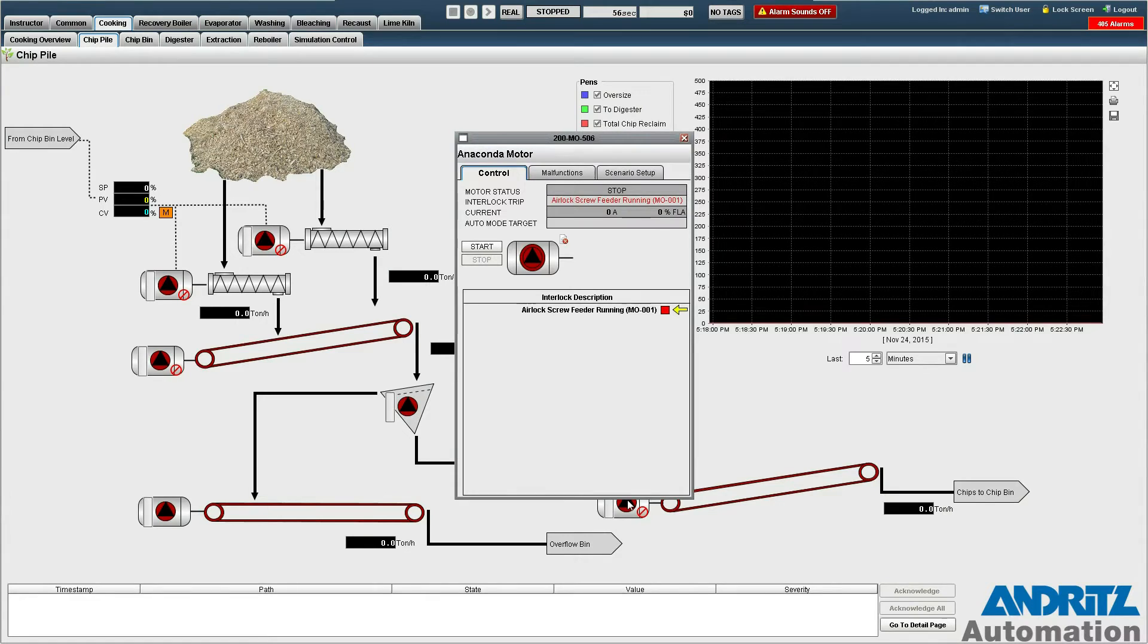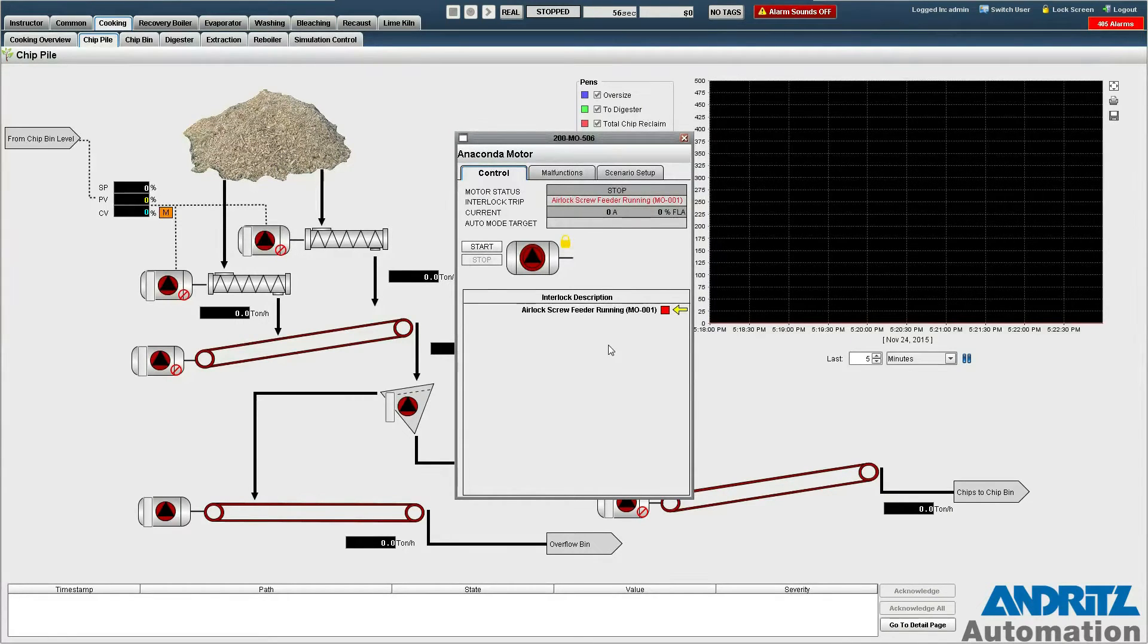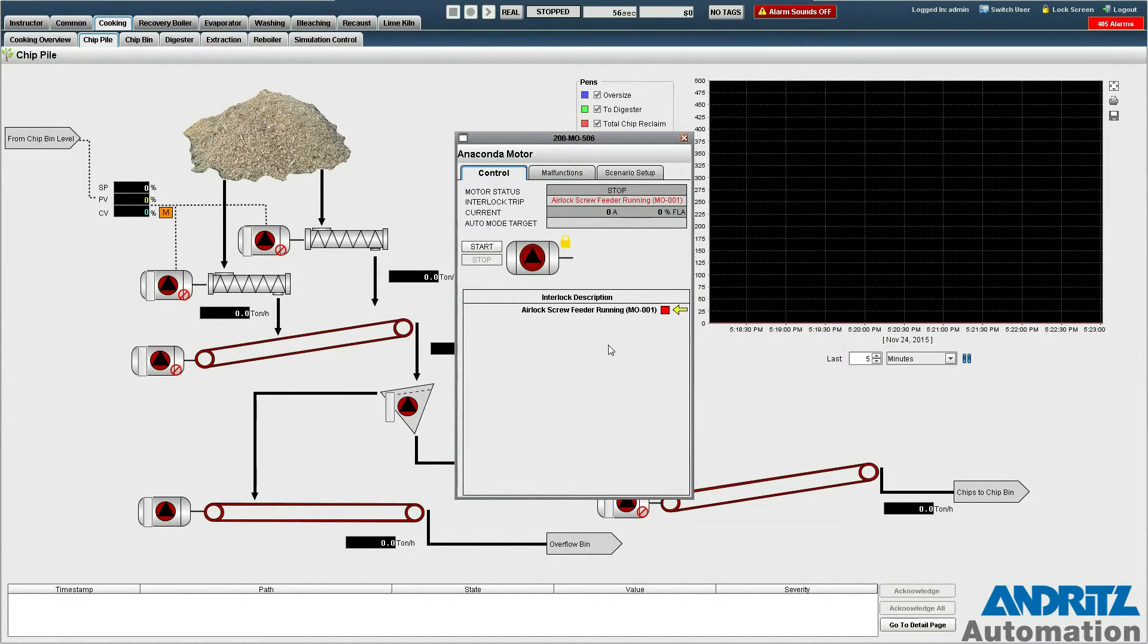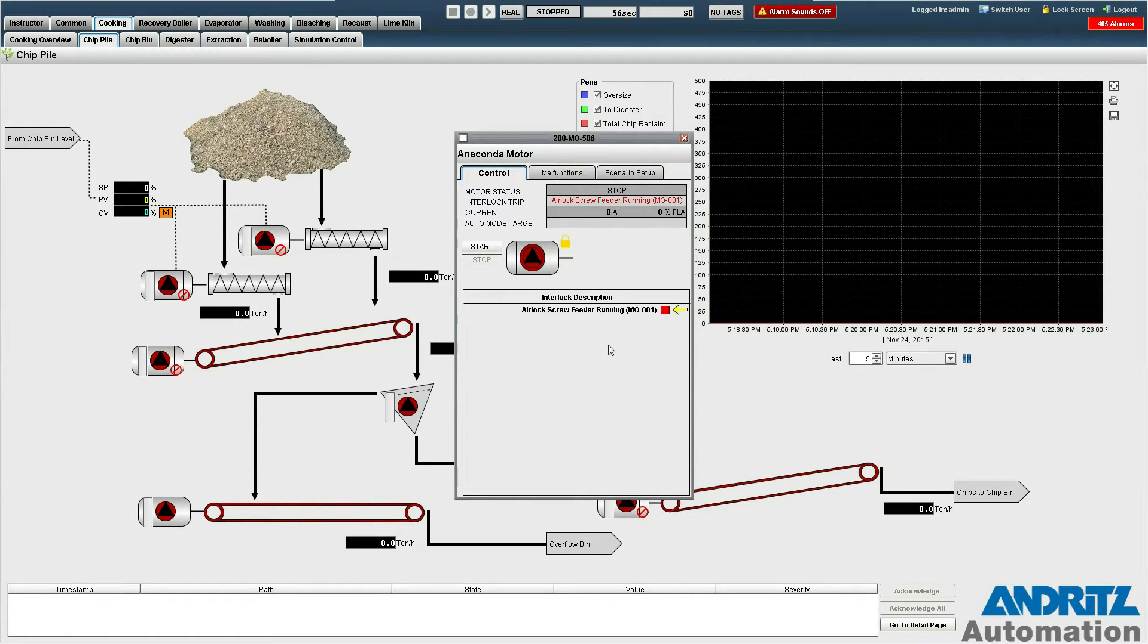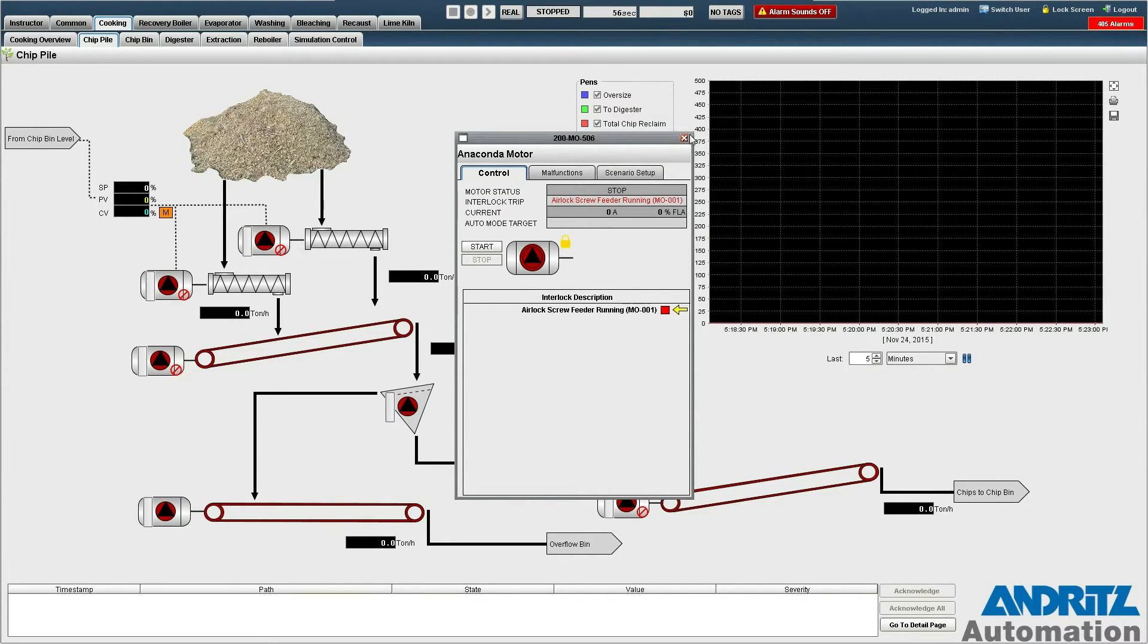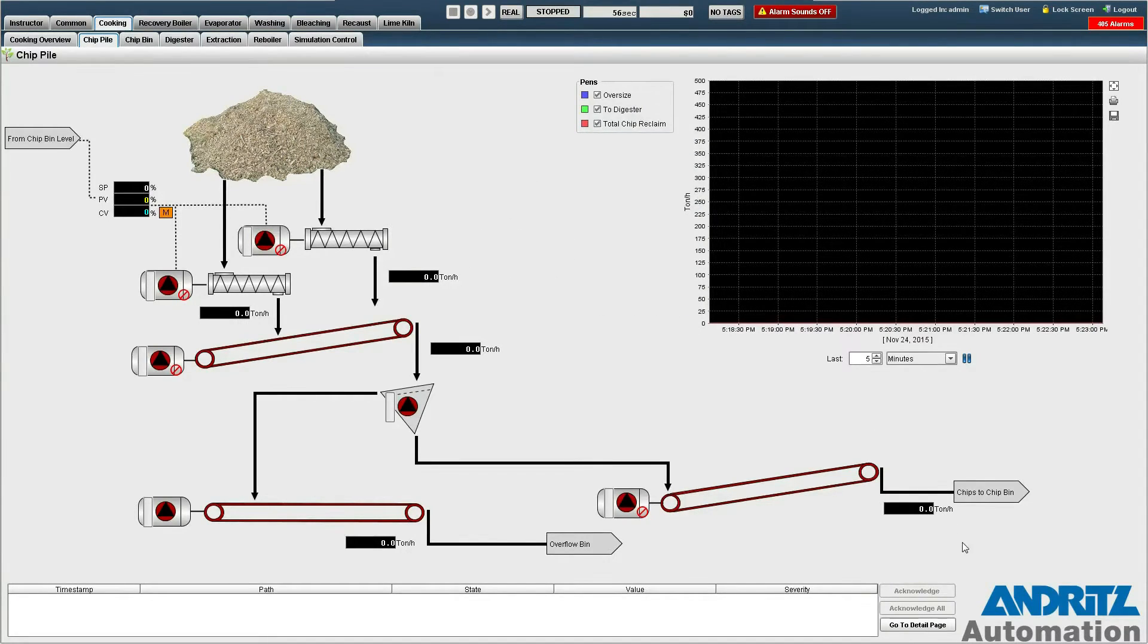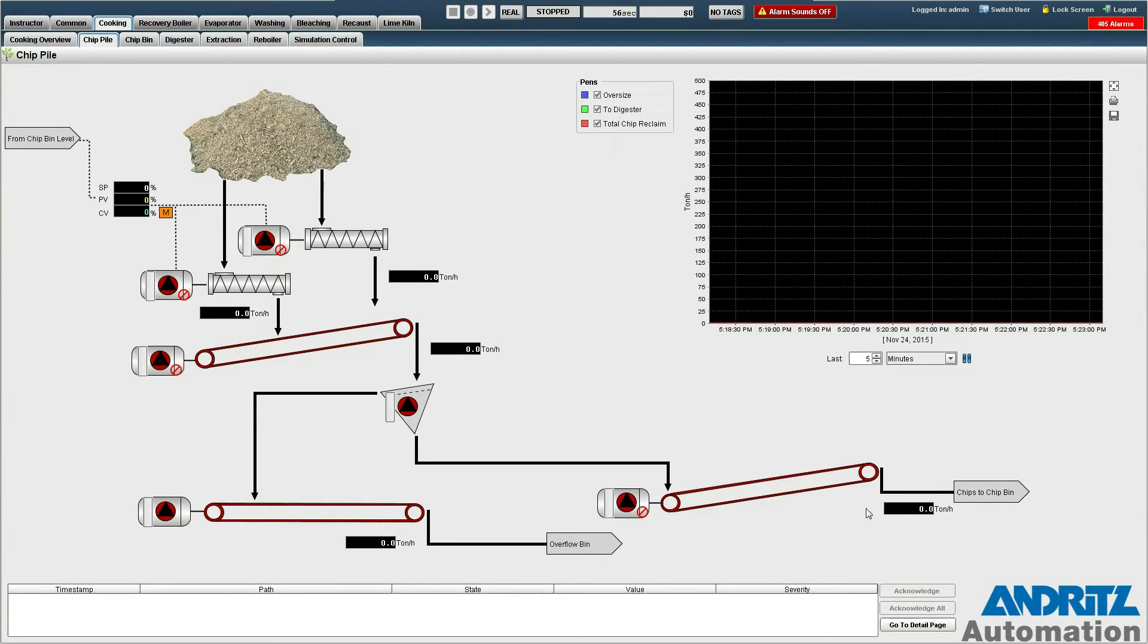Because of interlocks such as this one here the operator will need to start the entire train of material handling equipment down to the chip bin in order to start the feeder. Second we want to see a flow of at least 200 tons per hour to the chip bin measured here.